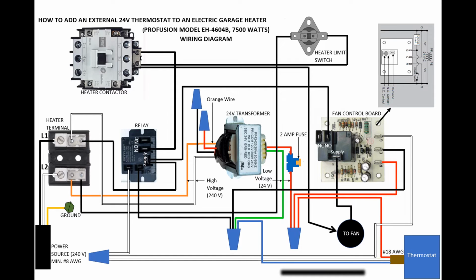Now let's take a look at the fan control board. Now this control board has a built-in relay, which would control the high voltage supply to the fan motor. Now this built-in relay would have the same principle as the relay that controls the contactor. Now the control board has 3 terminals for low voltage, R, C, and G, as you can see. The R terminal is connected to the 24 volts red wire from the transformer. This R terminal needs constant supply of 24 volts at all times. Now the C terminal is connected to the transformer's green wire, which is a low voltage common wire. And finally, the G terminal is connected to the thermostat's white wire, as shown here.